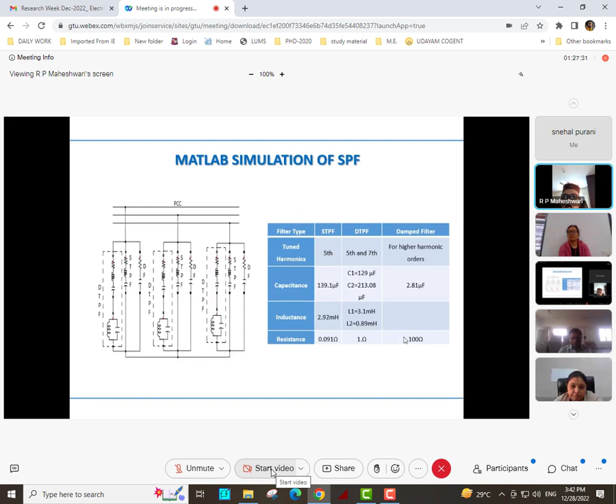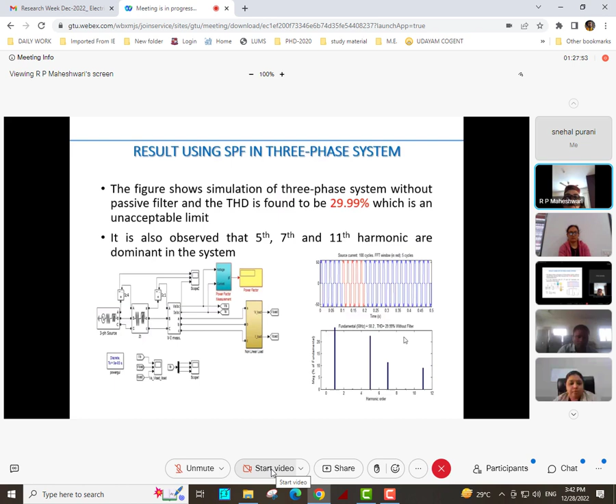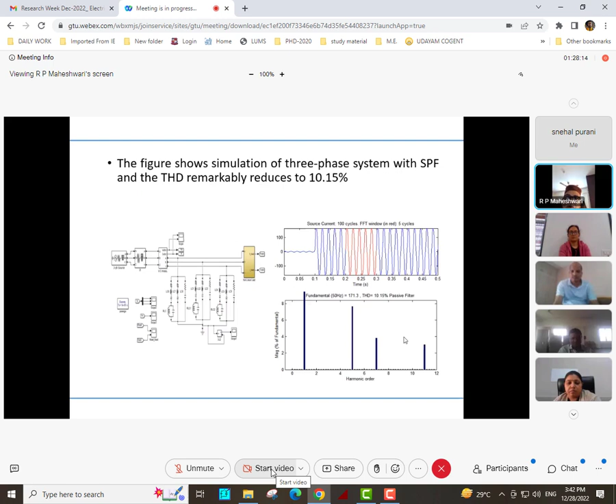Then the result using SPF in a three-phase system. The figure shows simulation of the three-phase system without passive filter, and the THD is found to be 29.99%. Fifth, seventh, and 11th harmonics were dominant. So definitely, because the THD was too much, it has to be reduced. With the SPF, the THD is remarkably reduced from 29.99% to 10.15%. It has been reduced due to the use of the filter.